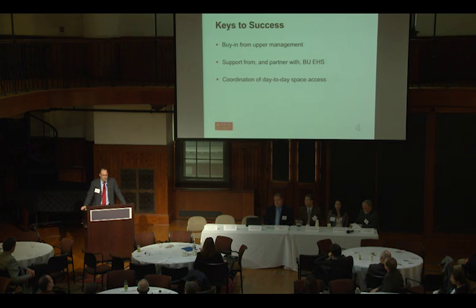The next key partner in this is it's not just about a technology or sort of money play, but really partnering with the right people in terms of safety. And our environmental health and safety folks were very good to work with. You got to remember when you're doing 20-something air changes or 16-something air changes, you start to see these linear feet per minute, exceeding 100, 200, 300, and that becomes a turbulent condition in these chemistry hoods, which is not safe. So they certainly were completely on board.